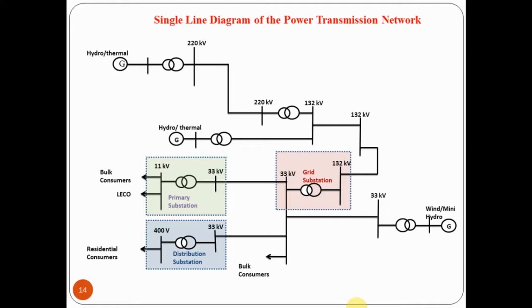So from the mini hydropower, wind power, or solar power plant, we connect at the 33 kV level to the system, and here it does not go through the transmission network. It goes directly through the 33 kV network. Not all the time, but most of the time it may stay within the village or the town itself. It may not go to the grid substation. This whole generation may be distributed from the 33 kV bus to these consumers.